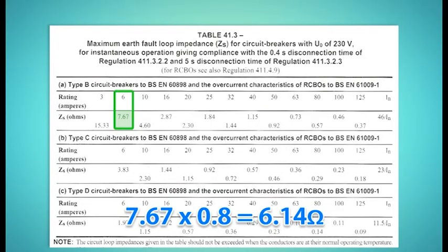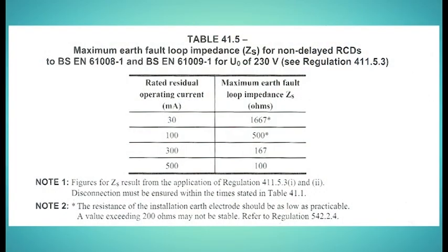This is then compared to the measured ZS. This check needs to be undertaken for each circuit. But where a non-time delayed RCD is used to provide either additional protection, such as you have here for the socket outlets, or for full protection, then the maximum values of ZS in table 41.5 may be applied instead of those in the other tables.